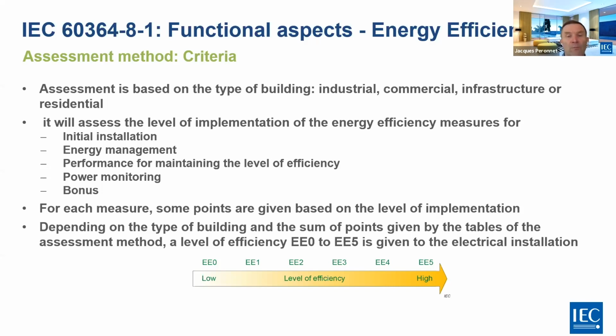So for each measure, some points are given on the level of implementation, and based on the type of the building and the sum of the points given by some table and the assessment method, you will have a level of efficiency which is going to be between 0 and 5, given that EE0 is the lowest level of efficiency, and where today the level EE5 is the highest. Probably in the future we will increase some levels, but for the time being, level 5 is the highest level. So this is what we today have for verification and test in the IEC 60364.